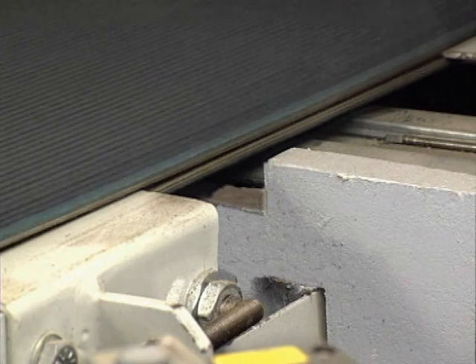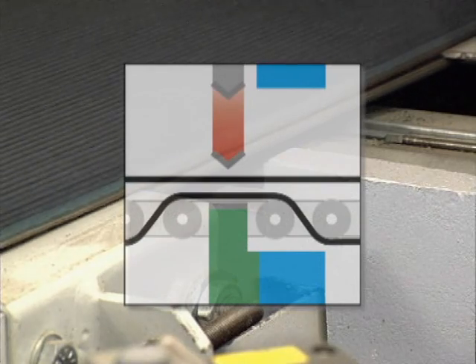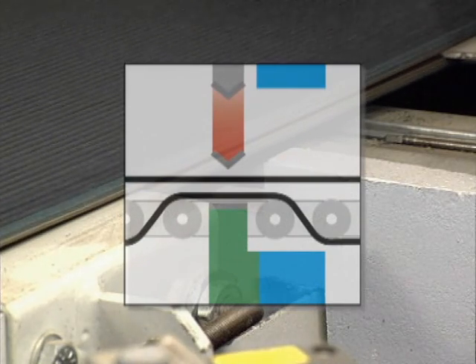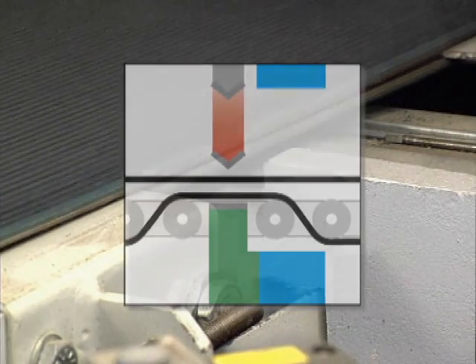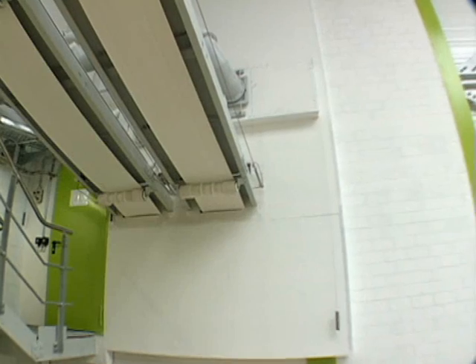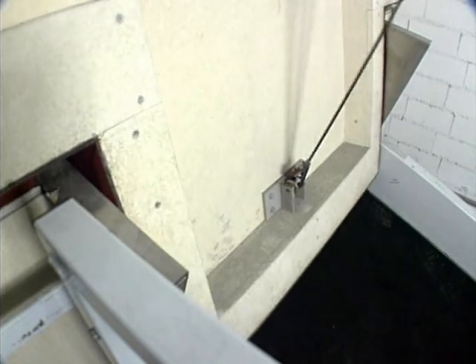The belt conveyors and the supporting constructions continuously run through the closure. A pair of rollers brings the lower belt near the upper belt. Another possibility is reversing the belts through a sleeve and foaming up at 120 degrees Celsius. These closures, using slide or flap solutions, are suitable for light and heavy inflammable conveyor belts.